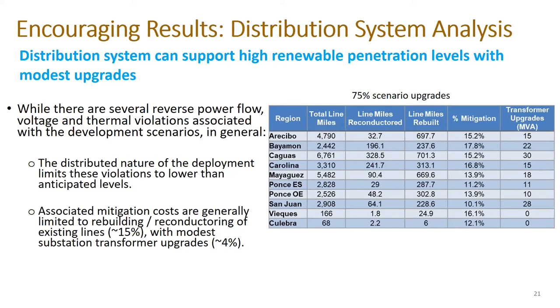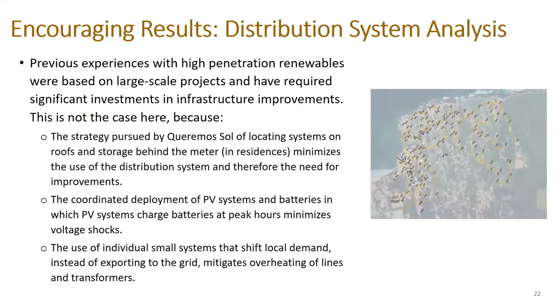We were getting values between 15 and 20%, much lower than I originally anticipated. And you'll see that because, again, we're not really moving a lot of power per se, the substation transformer upgrades were extremely modest. Maybe 4% of the total installed capacity. So the results in terms of the amount of mitigation that was necessary to correct the violations that we saw were very modest. Next slide, please. Let's talk about why we think that actually is.